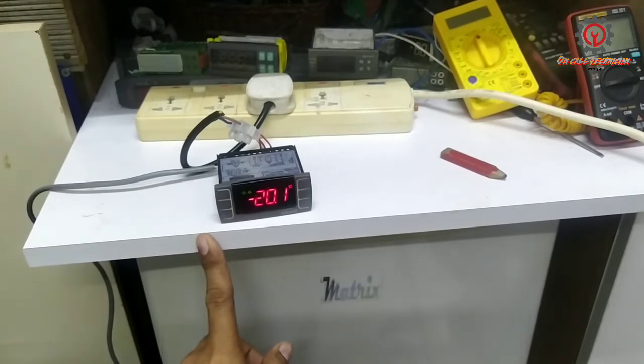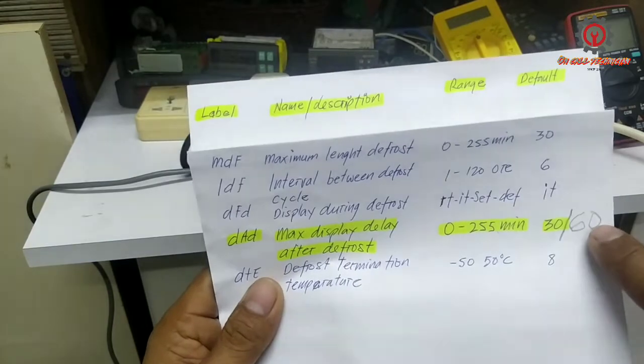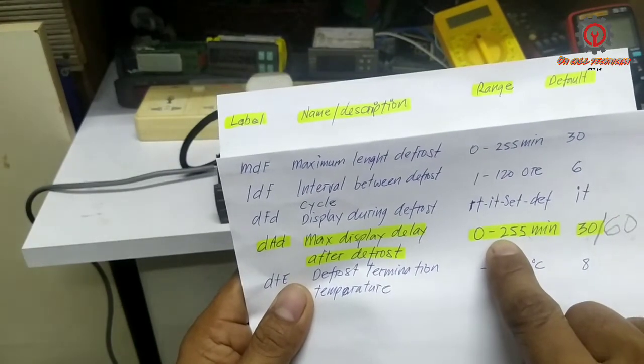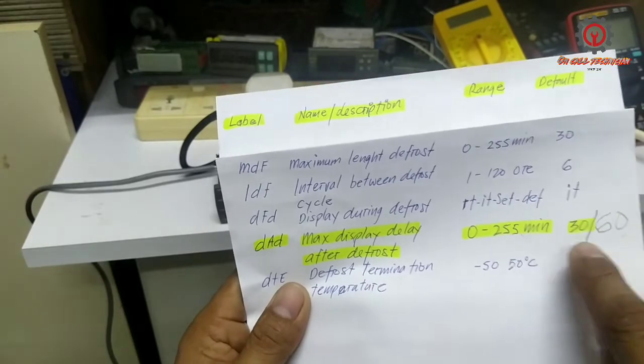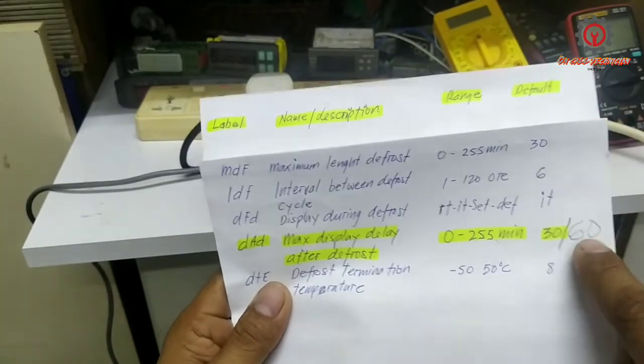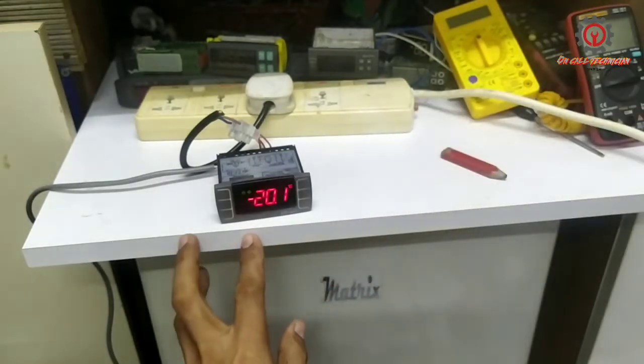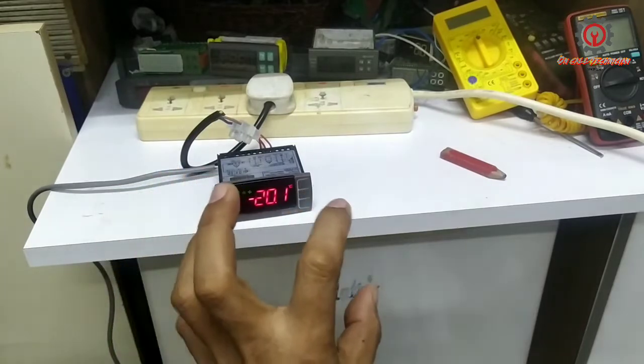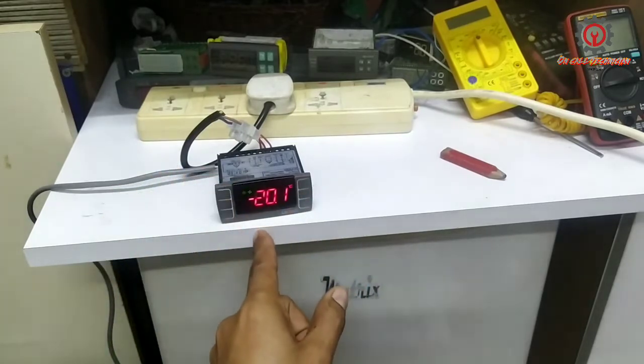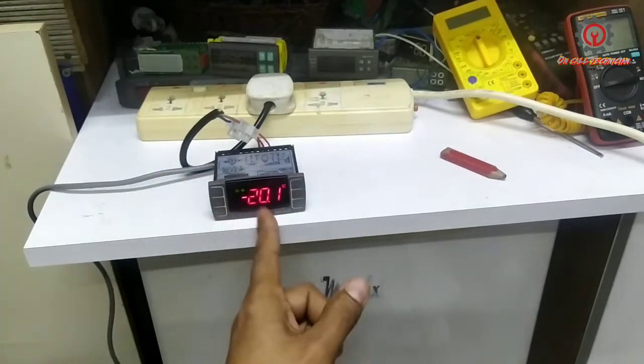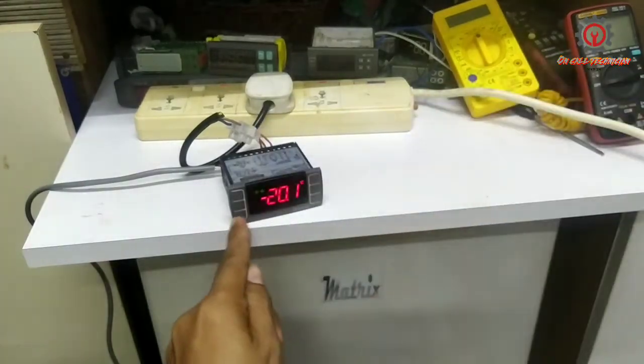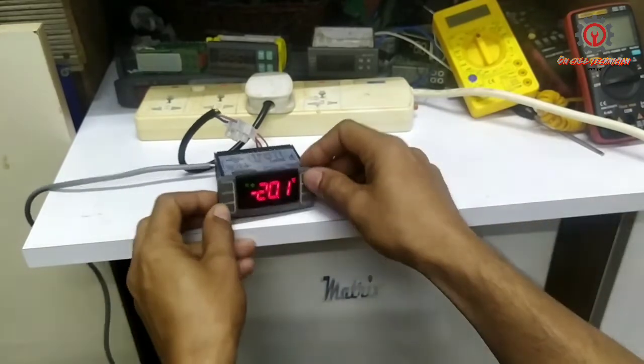That's how you're going to fix that. Do not prolong - for me this is max, although the manufacturer set it to 255 minutes. Just stay at 60, otherwise they will question you why after one hour the temperature is stagnant. They will ask you questions, maybe there's something wrong. I'm going to set the DAD to zero so you will see what is the temperature after defrost.